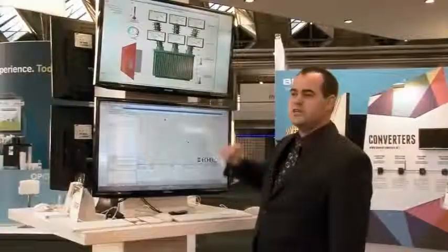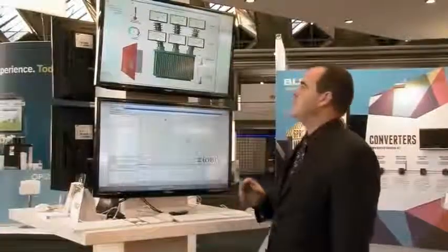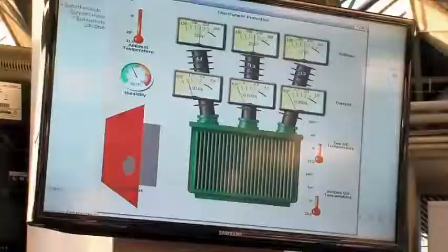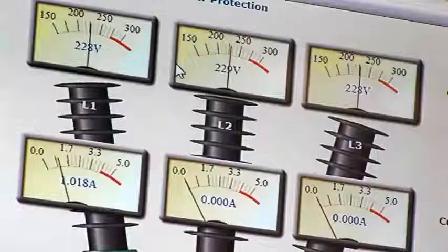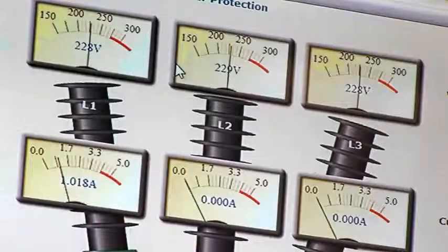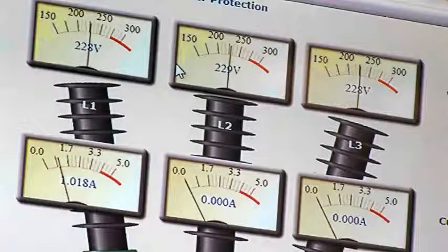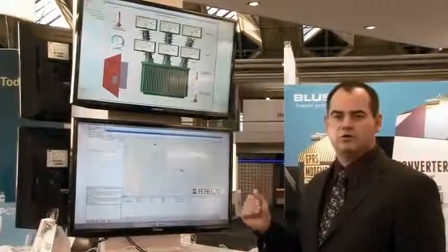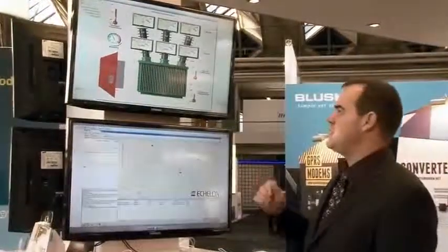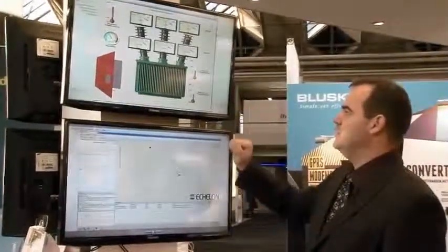On this view of a single transformer, we can see the information captured by the CTs. We see the voltages and the load information on the transformer. We get alarms when the transformer is overloaded or if we see a progression of the load increasing close to the capacity of the transformer.